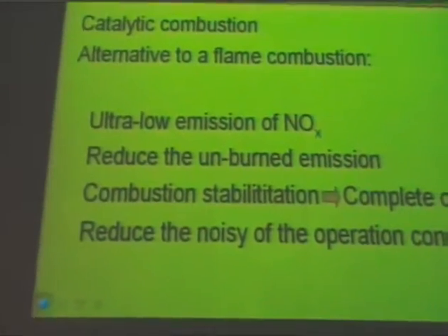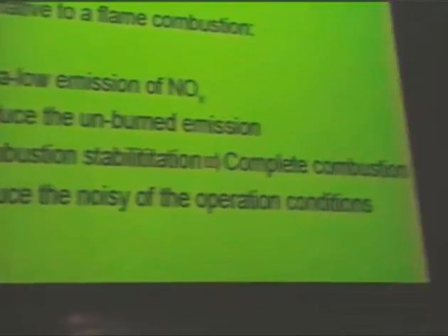Catalytic combustion is a very promising technology due to the ultra-low emission of nitrogen oxides. Several studies indicate that it is possible to limit this emission at less than 3 ppm. This is due to the lower temperature of combustion compared to conventional combustion. Catalytic combustion also reduces CO and hydrocarbon emissions, and the combustion is stable outside of the flammability limit and reduces the noise of operation.